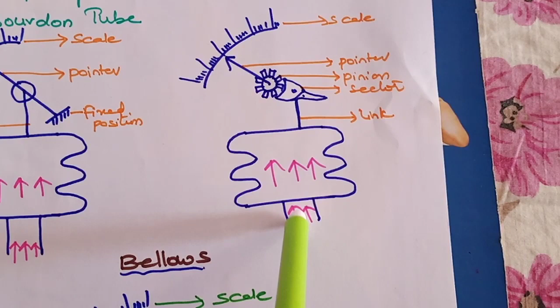As soon as the pressure is sent, the bellows starts expanding. As the bellows expands, the link connected to the sector moves the pinion, causing it to rotate. While the pinion rotates, the pointer connected to it starts deflecting and shows a value on the calibrated scale, indicating the pressure or force being measured. So this is about bellows.